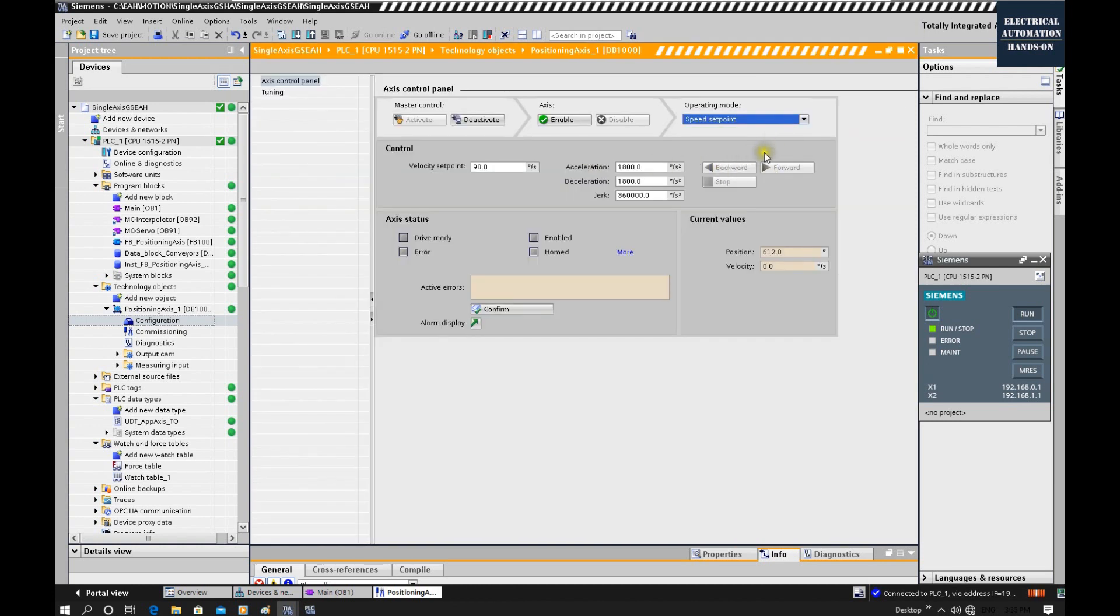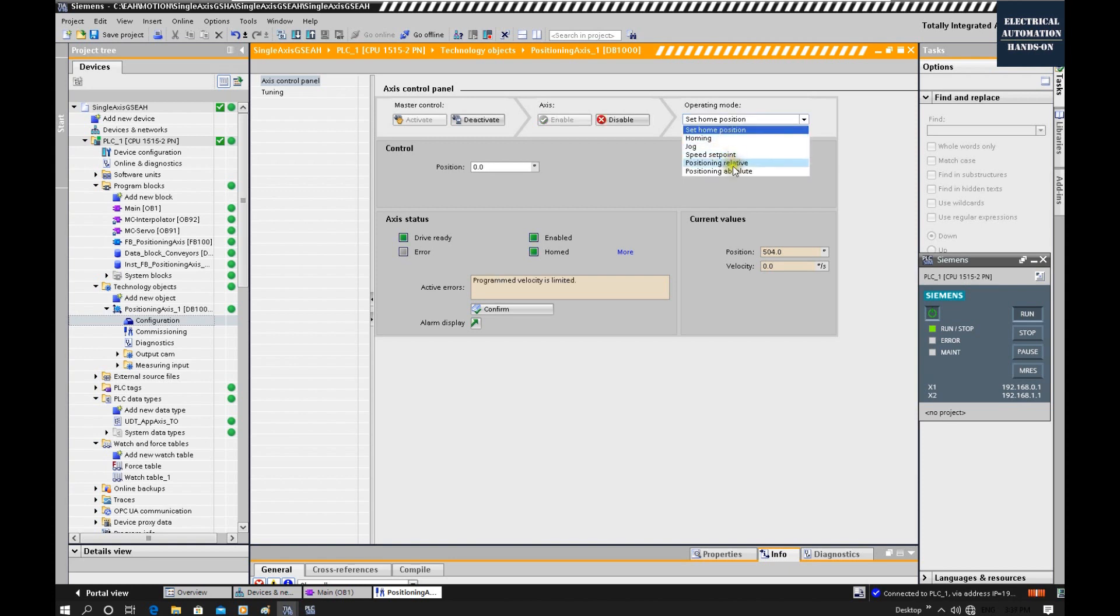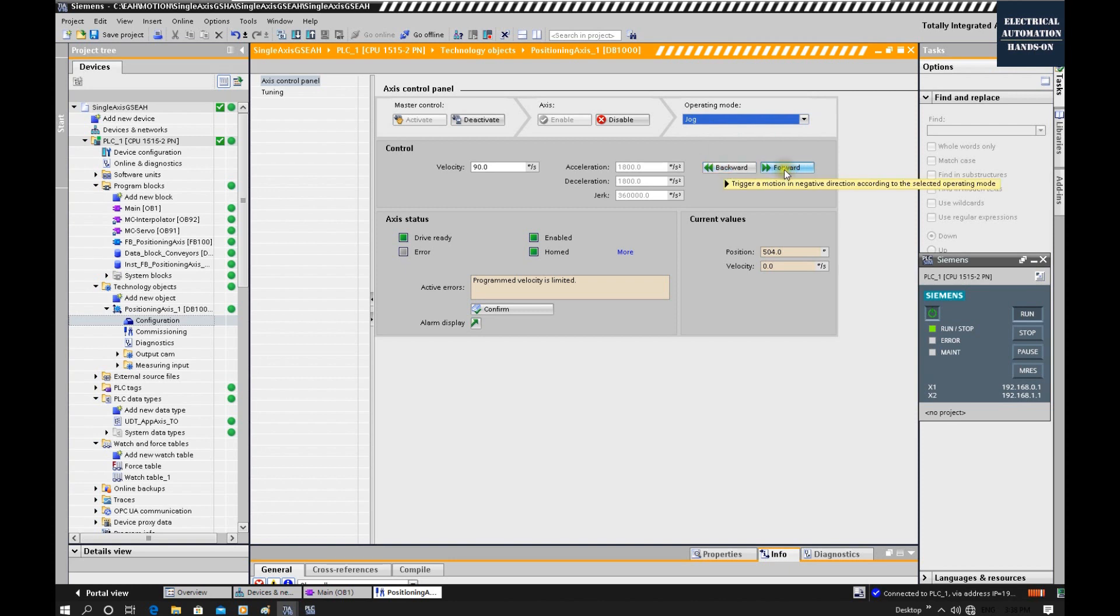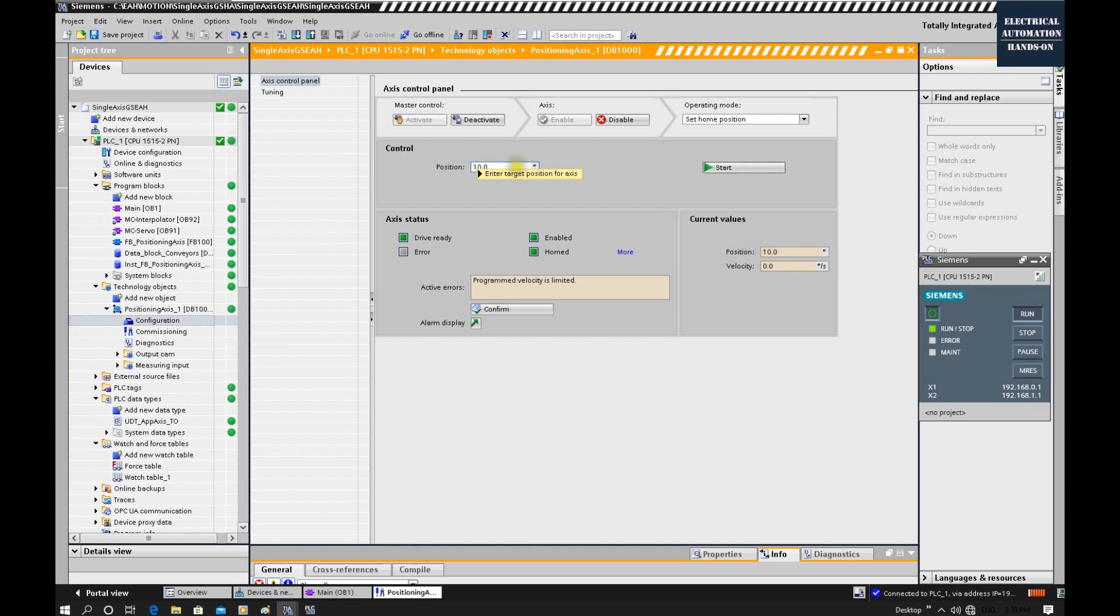After this direction verification, we can verify our actual distance if the system can run correctly. To verify the distance, we need to home our axis. We can jog using speed control or jog control to manually move this axis to our home position. After we reach this home position, we can select set home position and set this current position to home. This home could be zero or some value, the initial value. Let's assume the current position actually should be 10. Once we hit this start, it will set this home position. Now we set 10 degrees.